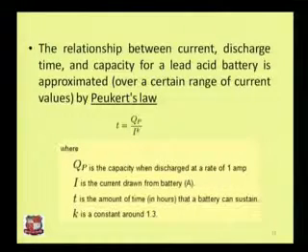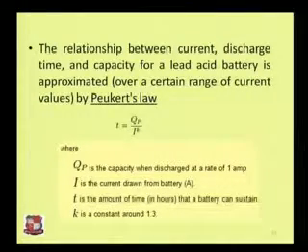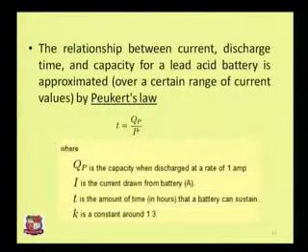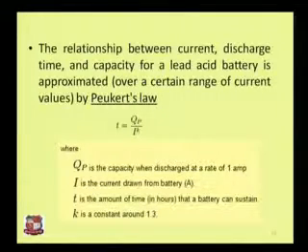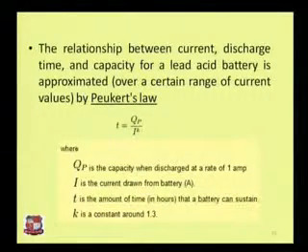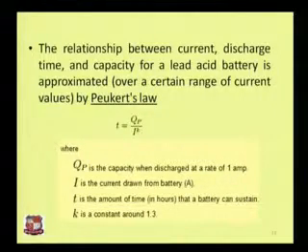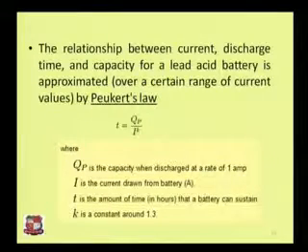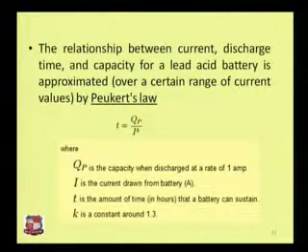By Peukert's Law, which shows the relationship between current, discharge time, and capacity of a lead acid battery, it is given by t = Qp / I^k, where Qp is the capacity of the battery when discharged at a rate of 1 ampere, I is the current drawn, t is the time in hours the battery can sustain, and k is a constant.